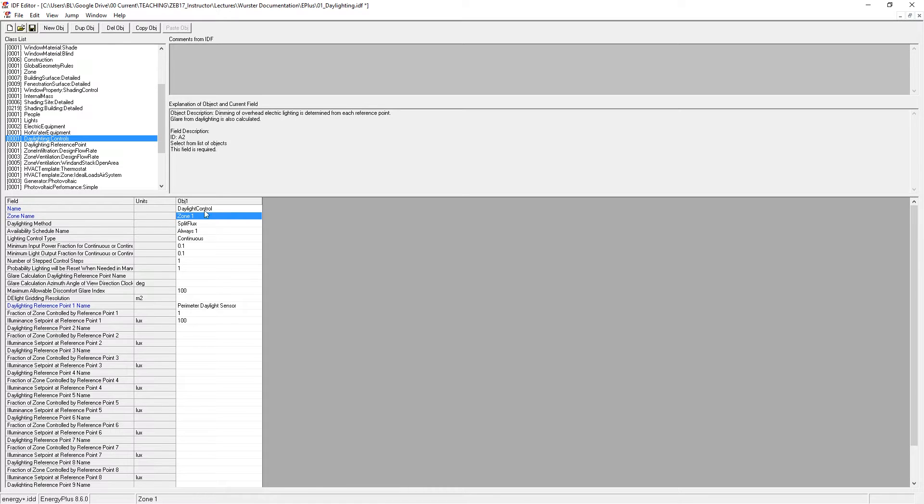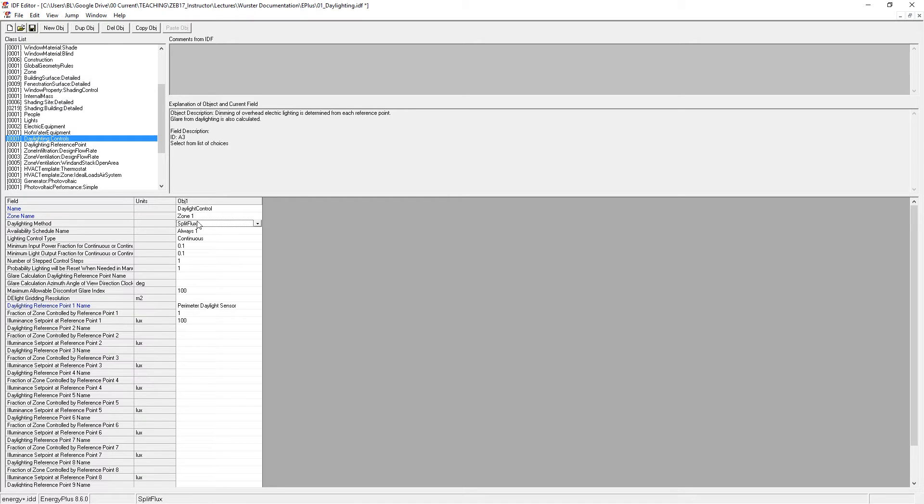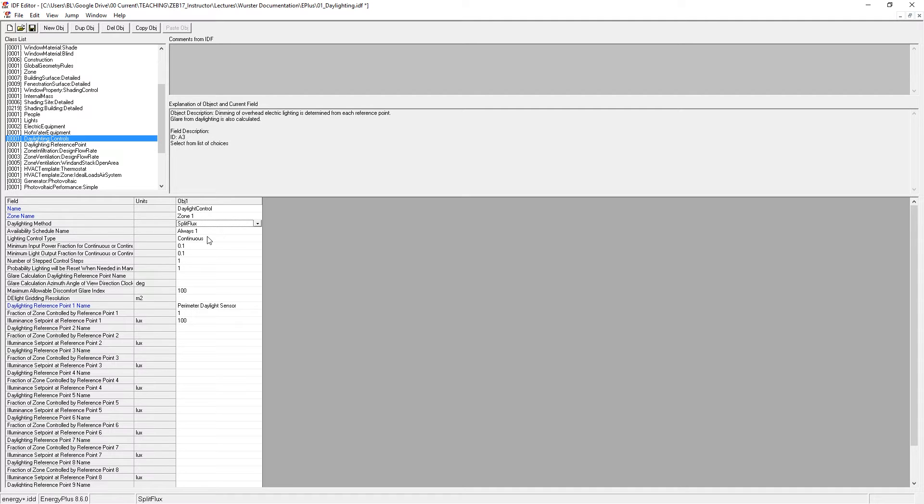So just to go through this, the name is daylight control. The zone is our zone. The daylighting method is the split flux method, which is not very accurate. So be aware of that. It tends to overestimate the amount of light that you have.